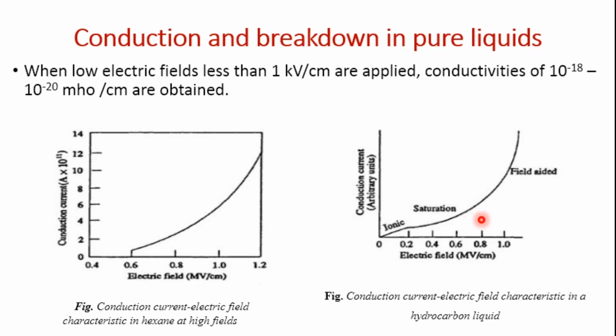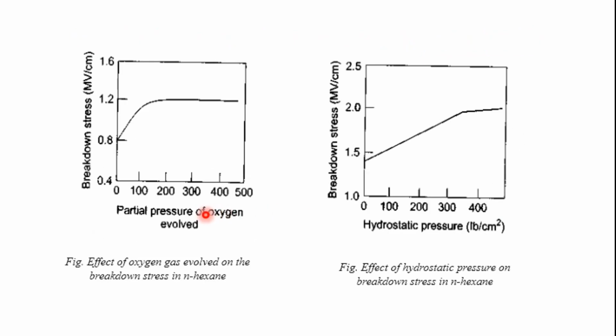The breakdown voltage mainly depends on the field, gap separation, work function of the material, and the temperature of the cathode. In addition, liquid viscosity, temperature, density, and the molecular structure of the liquid also influence the breakdown strength of the liquid. It has also been observed that the increase in breakdown strength is more if the dissolved gases are electronegative in nature, as from the partial pressure of the oxygen evolved. Similarly, in the case of liquids, hydrostatic pressure increases the breakdown strength. These are the two things explained here. So this is conduction and the breakdown phenomenon in the case of pure liquids.